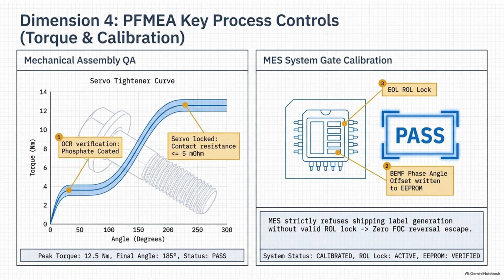And moving from the microscopic to the macro, the physical assembly of the bus bars is heavily automated. You can't just have an assembly line worker leaning on a torque wrench, because the contact resistance between the copper plates dictates the final parasitic inductance and thermal performance. They use robotic fastening systems equipped with optical character recognition. The OCR cameras verify the bolts have a specific phosphate coating to ensure a perfectly predictable coefficient of friction. And then the robot uses a torque angle method to drive the bolt. Yes, it doesn't just measure the twisting force. It measures the exact rotational angle of the bolt relative to the applied torque. This calculates the physical stretch of the bolt, guaranteeing the clamping force is perfect.